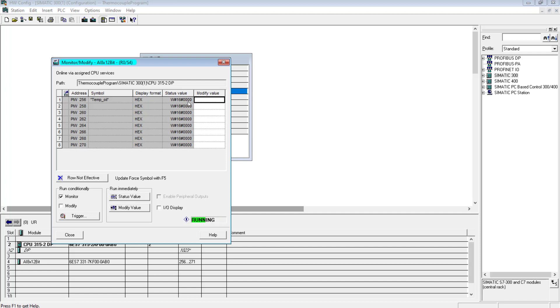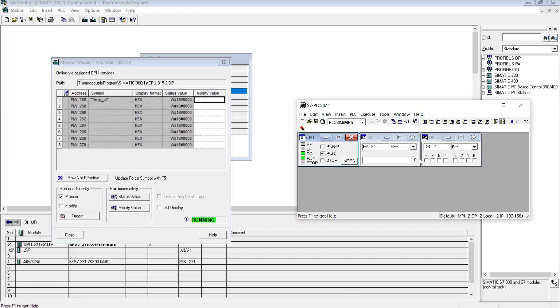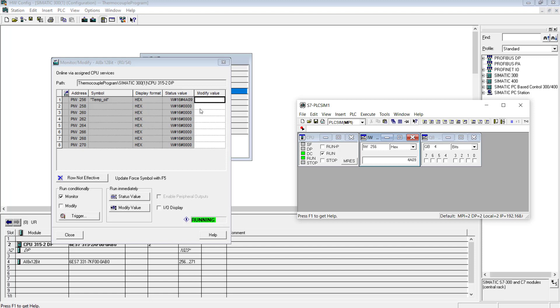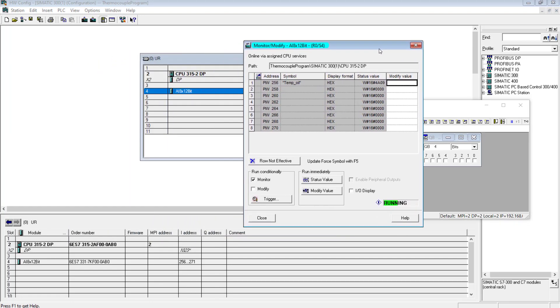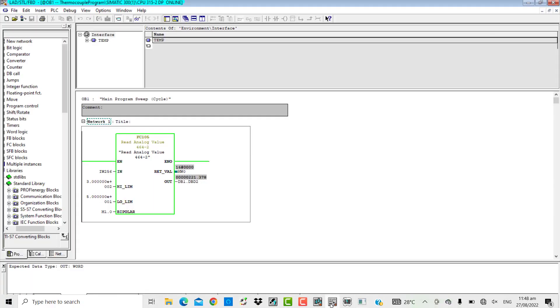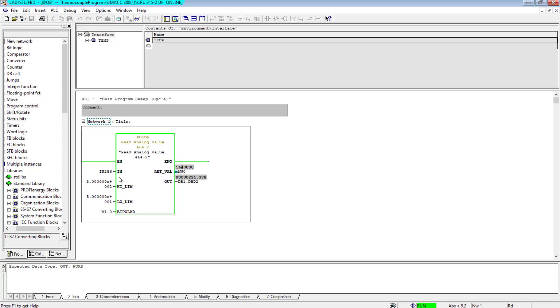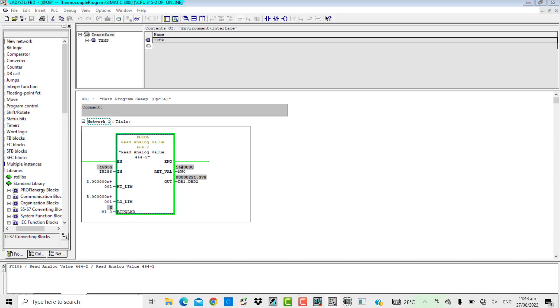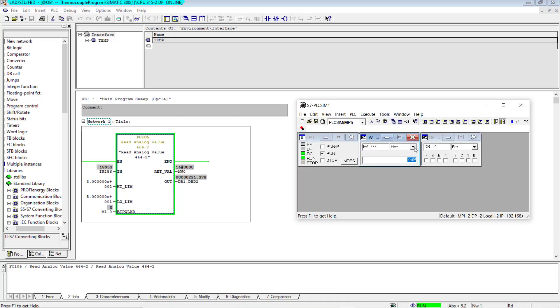If I monitor the analog input card, well over here is 0. Now I will try to give it a dummy value from the simulator. Go to the simulator and over here IW 256 is the address and I will try to give it 4A09. 4A09 is the hex value coming from the field, that is the hex representation of 4 to 20 milliampere, the actual 4 to 20 milliampere coming from the field. If I go to the OB1, over here you will find that 18953 - the decimal representation of the hex value. If I switch it to decimal, one eight nine five three, and that has been scaled to 221 degrees centigrade.